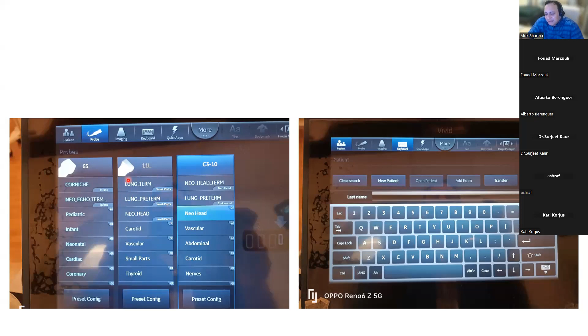For the preterms, we default to a frequency of 12 and a depth of about 3 to 3.5 centimeters, which is good enough, in my opinion, to give you a good breadth. How do I define that? For babies under 32 weeks, under 1500 grams, I'd use the preterm probe. For babies bigger than that, I won't hesitate to use the term probe. And I can interchange and play with the settings of using the probe with the term or the preterm small part setting to try and get the image quality that I actually want.